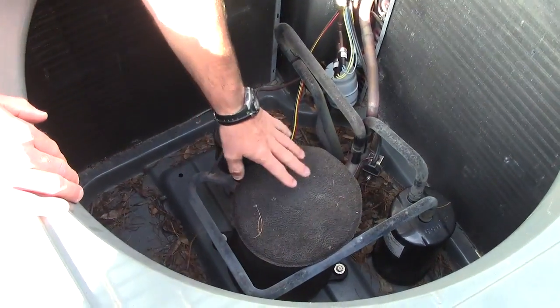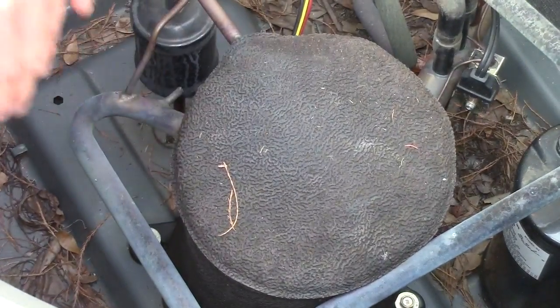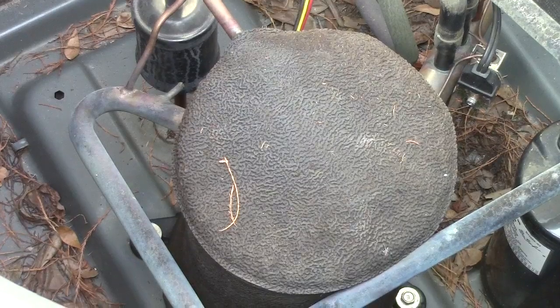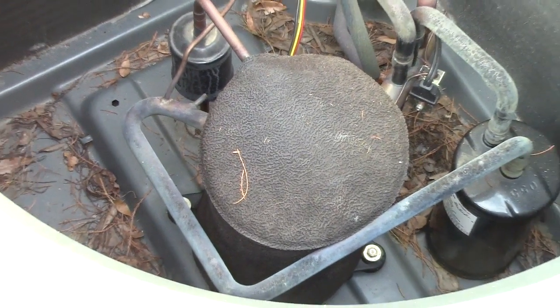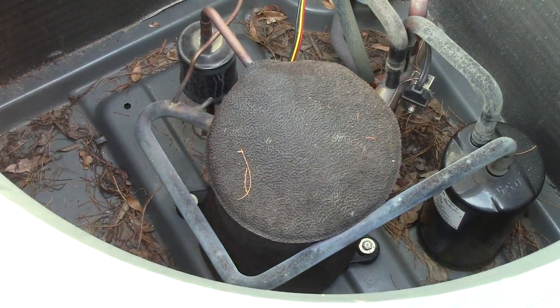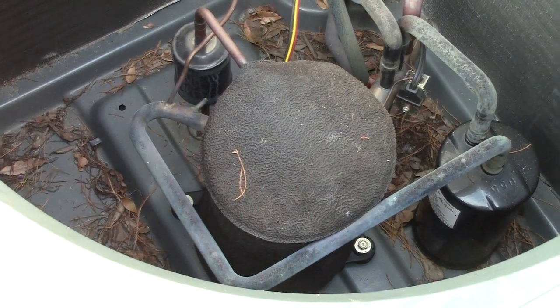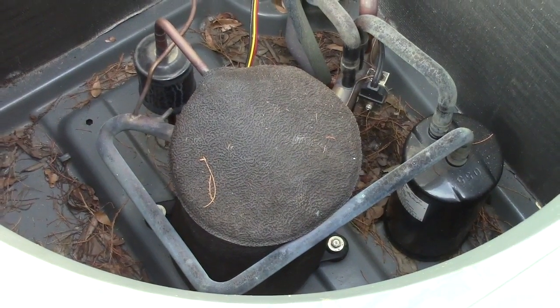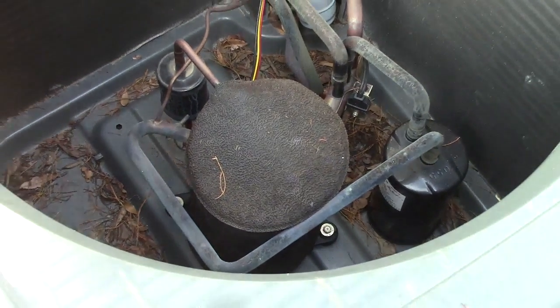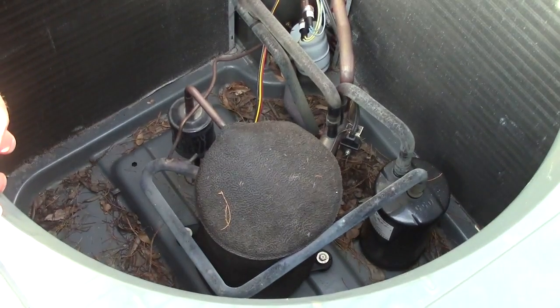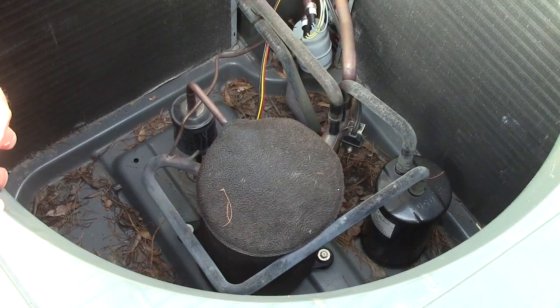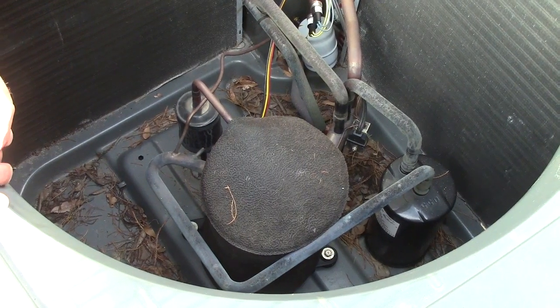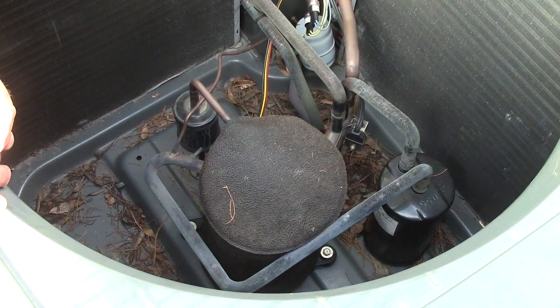Inside, dead center of the machine right here where I'm pointing, is the compressor. This component is the heart of the system. It pumps the refrigerant around and makes everything work. Without it, you have no air conditioning. It's very important to check it, make sure all the electrical connections are tight and clean, and that none of the wires have started to burn or chafe up against any of the piping.